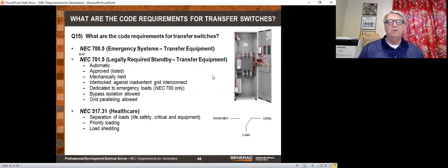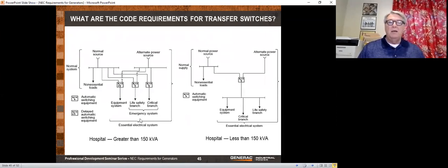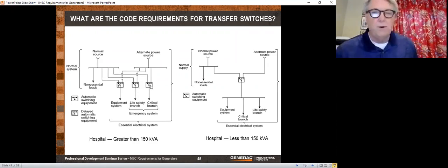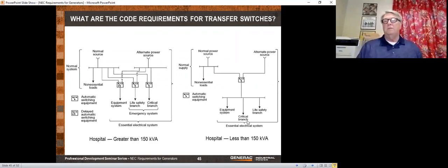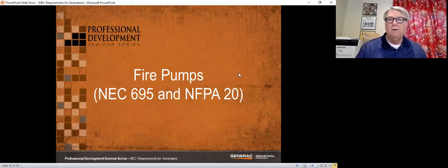What are the code requirements for transfer switches? Well, this is generally pretty easy. It shows all the requirements there: automatic, approved, mechanically held, and so on. But typically you buy a good quality transfer switch and it's going to have all those things, so it doesn't tend to ever be a real problem. Remember that if you have emergency circuits and legally required, or emergency and other circuits, they each need their own transfer switch because those circuits have to be separated. In a hospital, you need 1 transfer switch for equipment, 1 for life safety, and 1 for critical. Life safety is basically your building evacuation in your hospital. Critical is your emergency rooms and your operating rooms. But they said if it's like a portable hospital, so it's less than 150 kVA, they will allow you just to have 1 transfer switch.